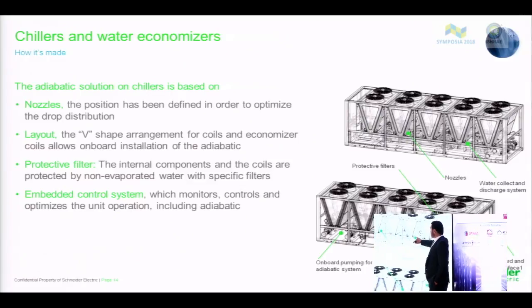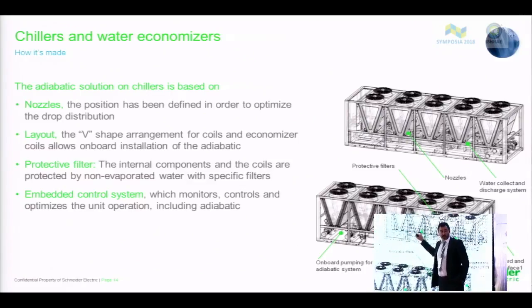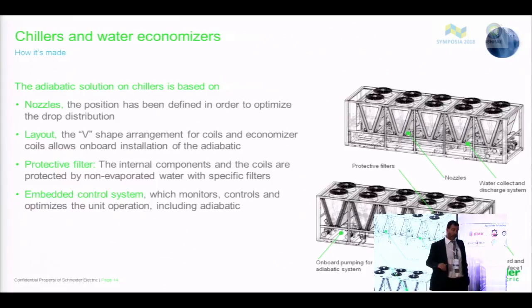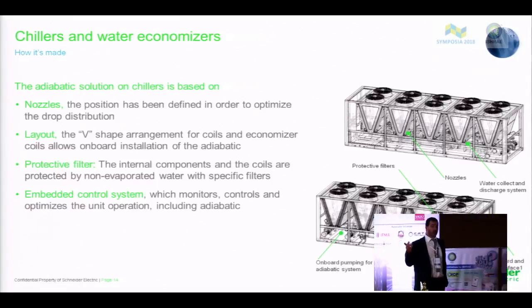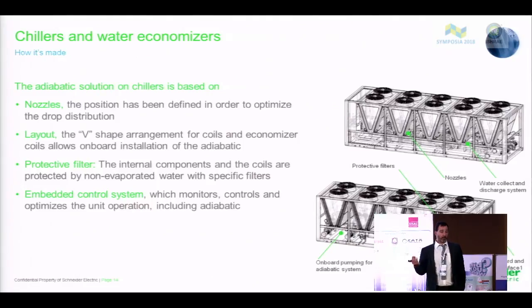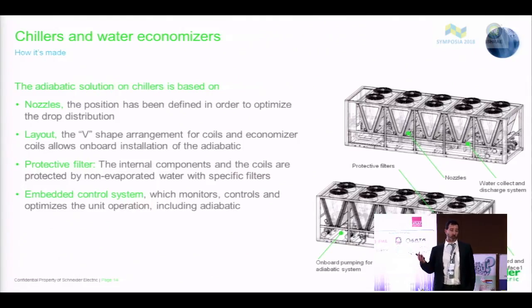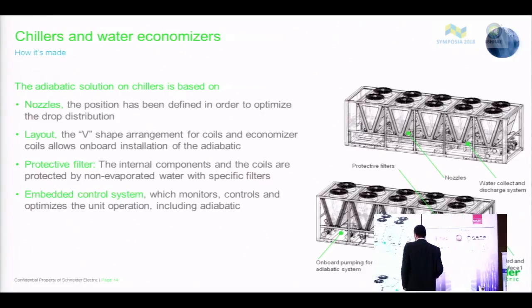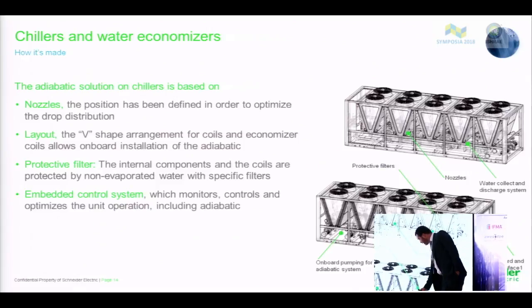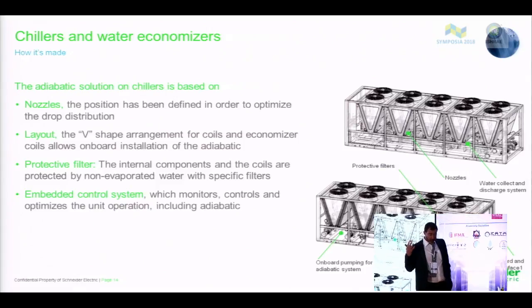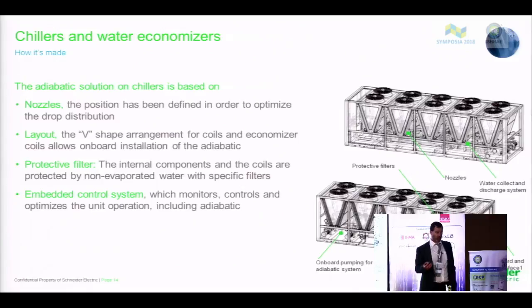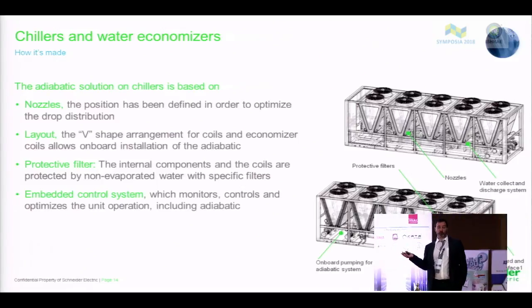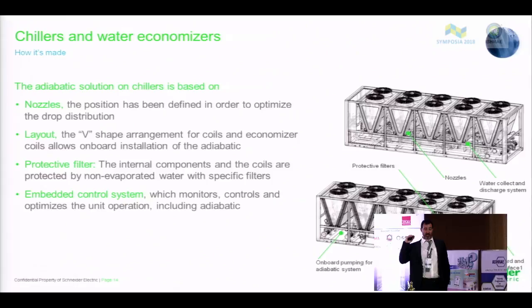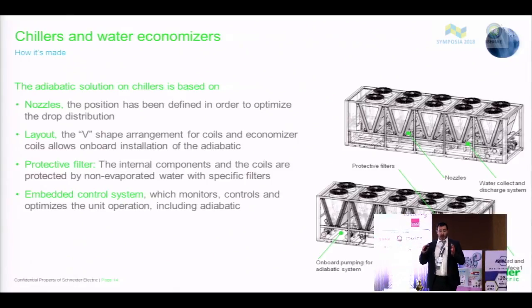There are typically some high pressure sprays in front of the coil. It is important that the spray should not keep the coil wet, but wet a sort of media in front of that, because otherwise the coil is corroded. And this wet media, this filter, allows a lower temperature, because the media allows the temperature to drop from the dry bulb to a mid temperature between dry and wet bulb.